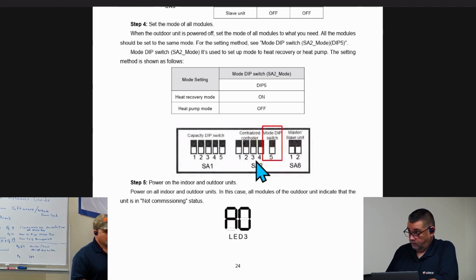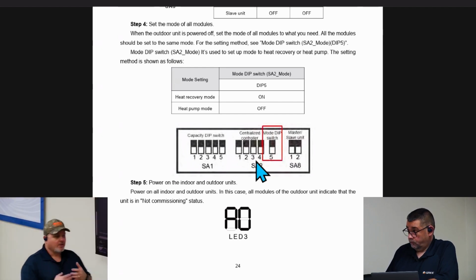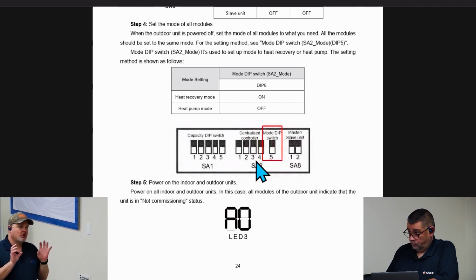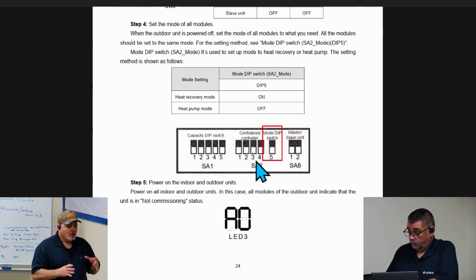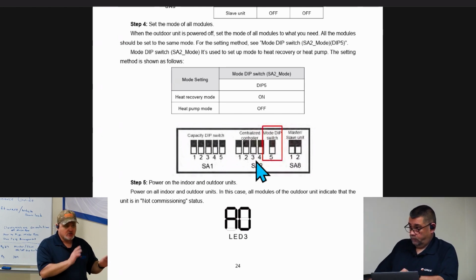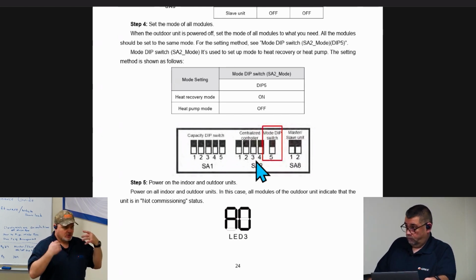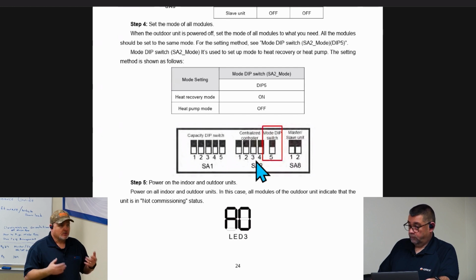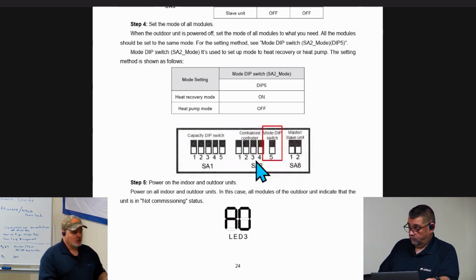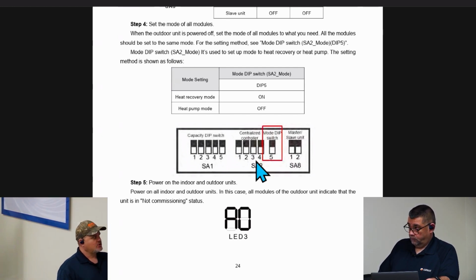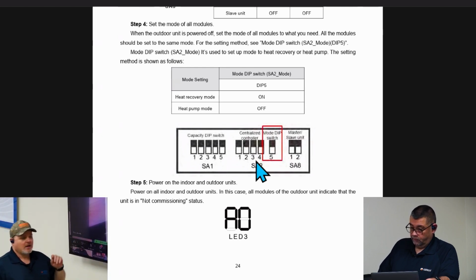These centralized controller dip switches: the master, as far as communication goes for central control, is the very first unit in your sequence. You are not going to change those dip switches. That's going to be the master for communication, not master-slave for units, master for central control or cool automation, okay? Then your second unit, you're going to change the dip switches at SA2 to make that unit number 2 or system number 2.